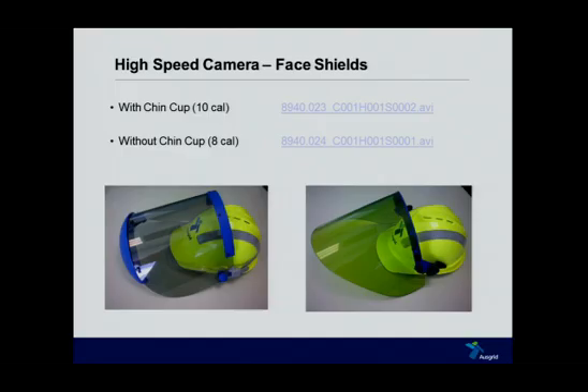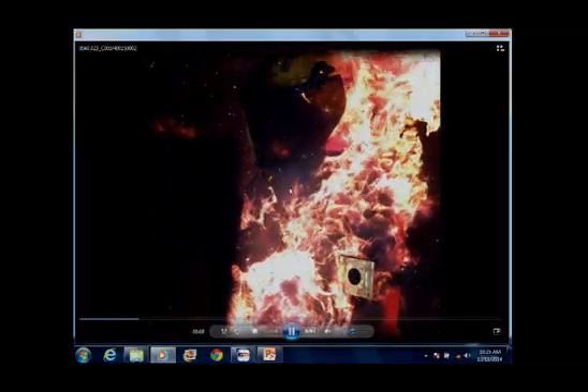This first one is the face shield with the chin cup. This is immediately after the arc, and you'll see that although there's some heat up here, the chin cup is doing the job it should. As the flame comes up the shirt, you'll see the chin cup does its job in preventing the flame from getting up under the visor.